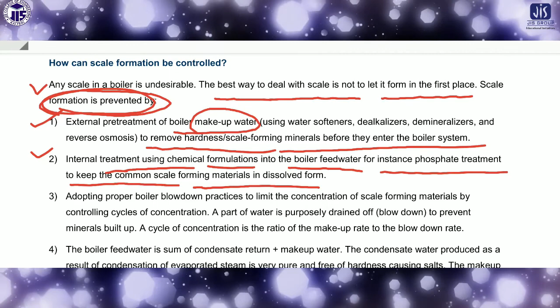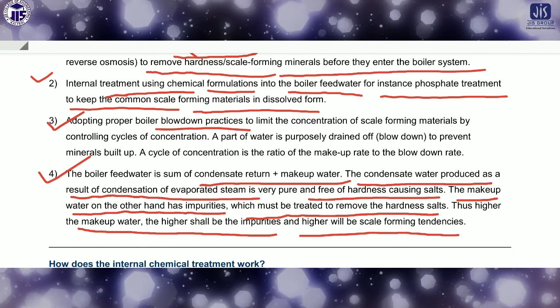The boiler feed water is a mix of condensed water and makeup water. The condensed water produced as a result of the condensation of the evaporated steam is very pure, as we already discussed, and free from hardness causing salt. The makeup water on the other hand has impurities, which must be treated to remove the hardness salt. Thus, the higher the makeup water, the higher the impurities and the higher the scale forming tendencies. So if the amount of makeup water is increased in the boiler, then obviously the chance of scale formation will be higher. In this way we can control the scale formation.